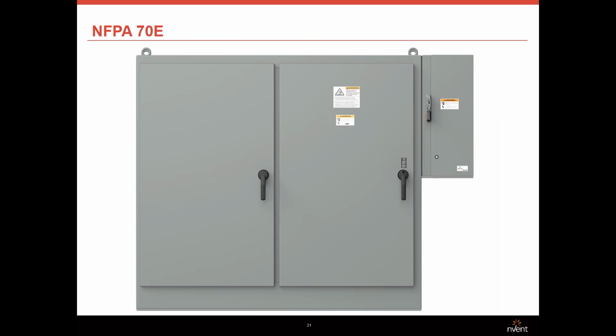So to repeat, once an IEEE 1584 assessment of control cabinets has been completed, the proper labeling has been put in place, and the proper PPE required based on the hazard of the enclosure is established, we look to NFPA 70E. Remember, NFPA 70E is an employee workplace standard.